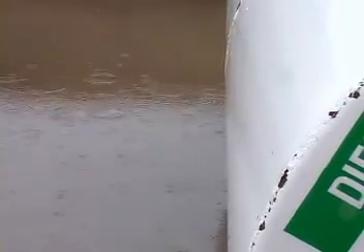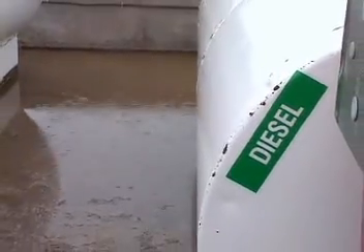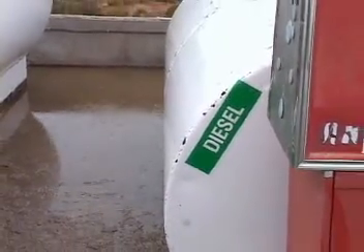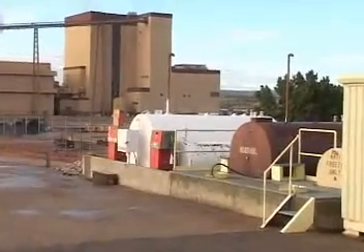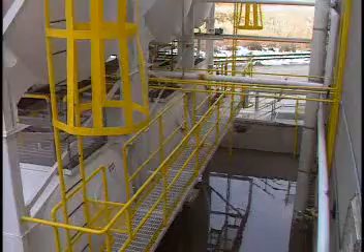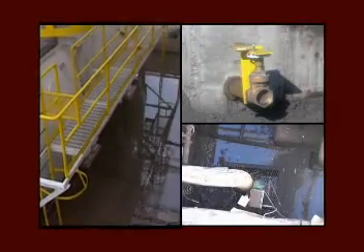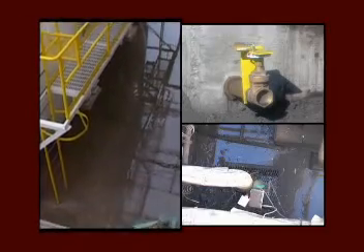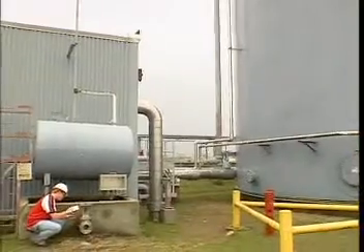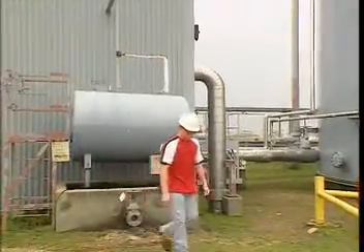There is one waste that has to be handled with extra care: the rainwater and snowmelt that can accumulate in secondary containments or other open-top structures. This secondary containment protects the gasoline, diesel fuel, and used oil tanks against leaks or rupture, but rainwater may have to be drained periodically. Many such structures have drain valves, pipes, or ejectors to allow draining. These devices must be kept securely closed at all times, except while actually draining rainwater.